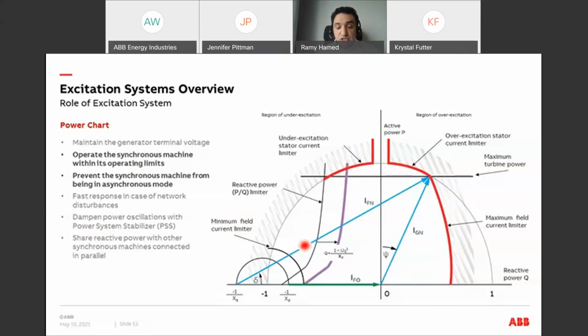We can see here that the generator is able to provide active power or megawatt to the grid, which is controlled by the turbine. And it can also supply or absorb reactive power or megavar to or from the grid, which is controlled by the excitation system. The power chart is then divided in two areas. The over-excitation area, where the generator will be supplying reactive power to the grid, and the under-excitation area, where the generator will be absorbing megavar from the grid.